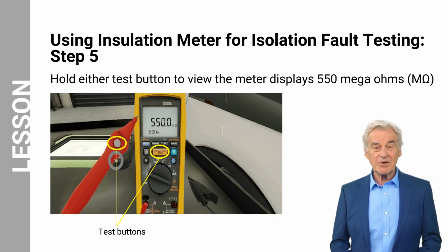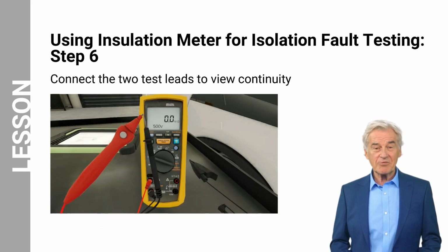Step 5. With the test leads not connected, press and hold the test button to view how your meter displays an infinite measurement. The meter will display 550 mega-ohms when measuring an open circuit while set to the 500-volt range. Step 6. Perform a continuity test by connecting the test leads. With the test leads connected, hold either test button. The meter displays 0.0 ohms, an uninterrupted circuit known as continuity.